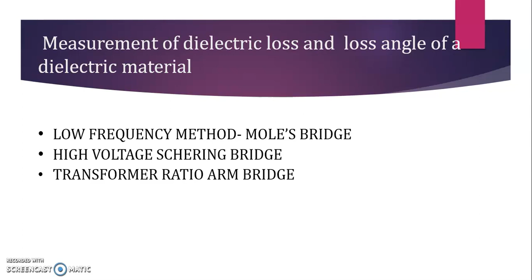This is primarily devised to measure the dispersion in insulation of the installed equipment and gives a reliable measure of the moisture content in the insulation. It is very well known that the dielectric dispersion increases rapidly with the decrease in frequency, and hence a more sensitive measurement is obtained at a low frequency circuit.